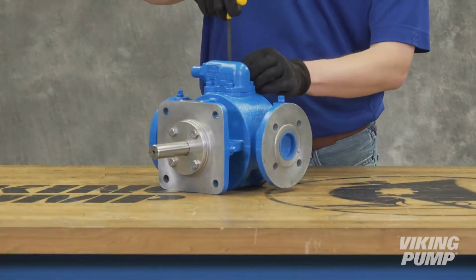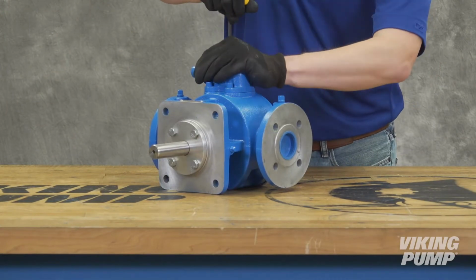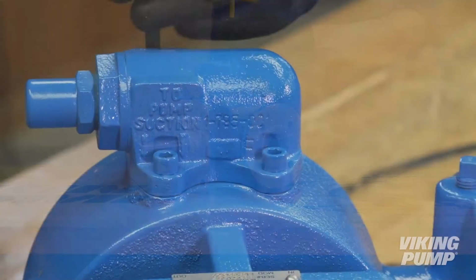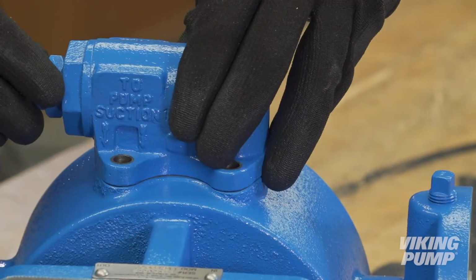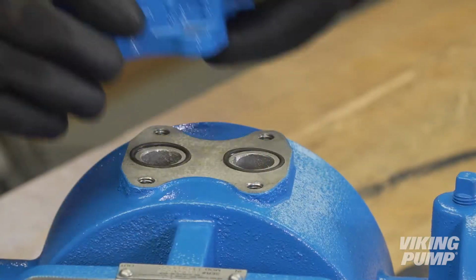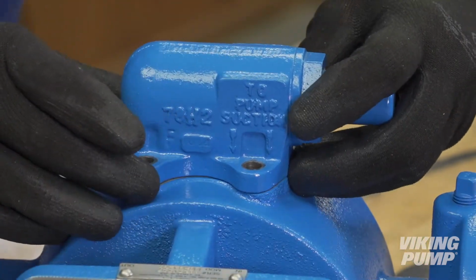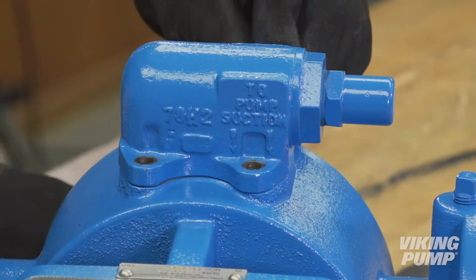The first item to address is the relief valve orientation. Remove and rotate the relief valve 180 degrees. Reinstall the valve so that the adjusting screw cap is pointing toward the new suction side of the pump.